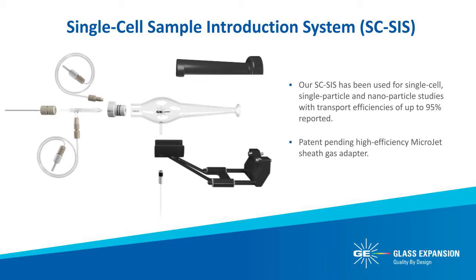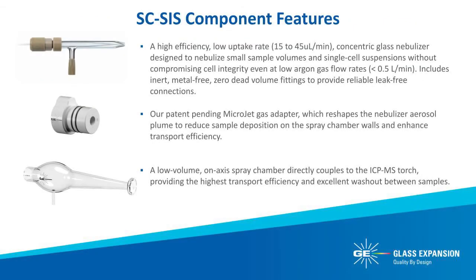Now let's take a closer look at these three key components. The nebulizer is a high efficiency design based on Glass Expansion's trademark Micromist nebulizer. The Micromist HE is a concentric nebulizer designed to nebulize limited sample volumes and single cell suspensions without compromising cell integrity at low argon gas flow rates.